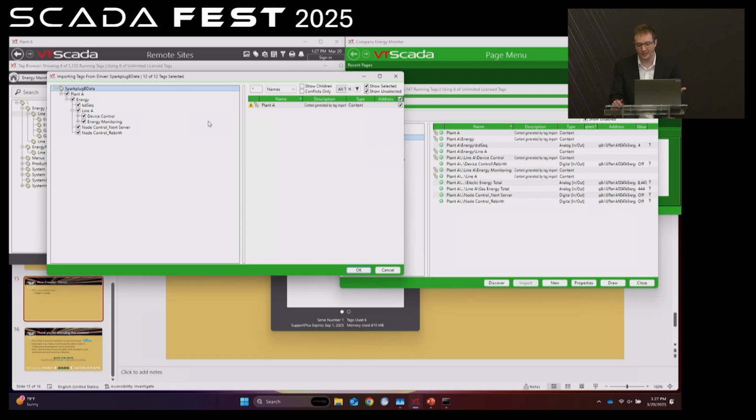The downside to automatic tag creation is if I did cut and paste a tag out of here, the next time a birth message came in, it would rebuild it, because VT-SCADA would go, hey, I don't see a tag here, I should add it. So that's the only downside to leaving automatic tag creation on. It's really a great tool initially to set up. And then typically, I would say once you know you have everything in, turn it off. Or turn it on for select periods.